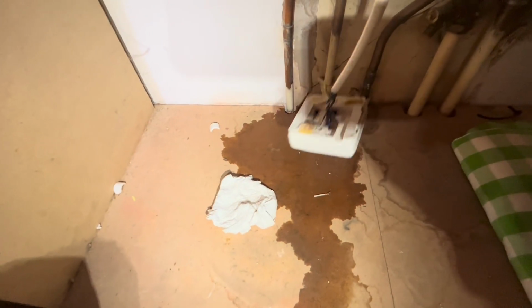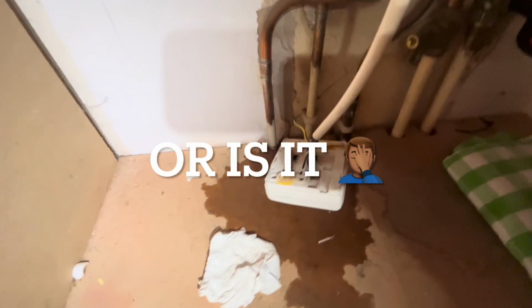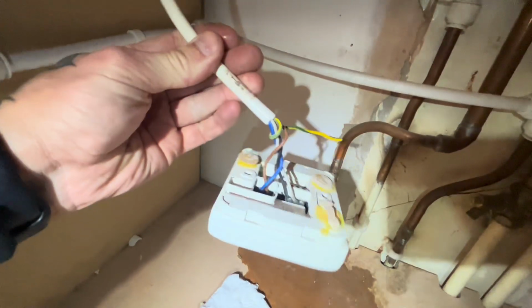Sorry. This is the problem. This has been dangling down here, and the flow valve has got a little leak on it from the fibre washer. It's dripped straight into that, and obviously blown the circuit, blown the receiver. So we'll swap the thermostat, drain it down and sort that leak out, and mount this to the sodding wall.